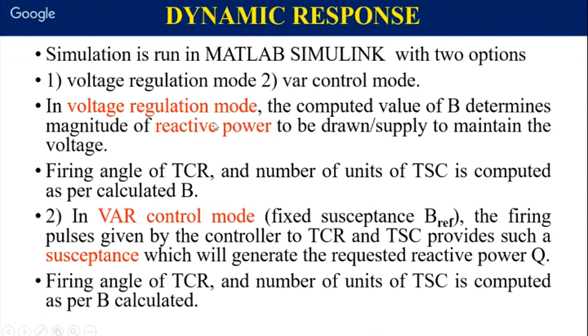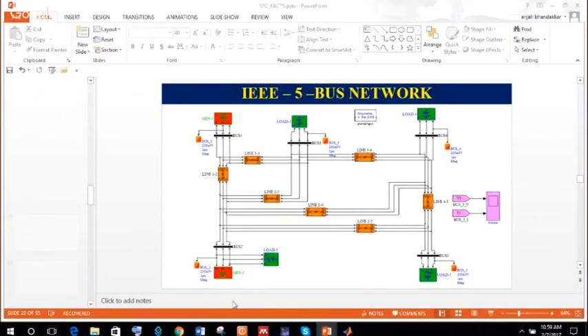Now there are two main things that you can see here. One is voltage regulation and one is VAR control mode. In voltage regulation, voltage at a particular bus will be maintained, and in VAR control, reactive power will be maintained, and according to this requirement, firing pulses will be generated, and the number of TSC that are to be inserted is decided by the controller.